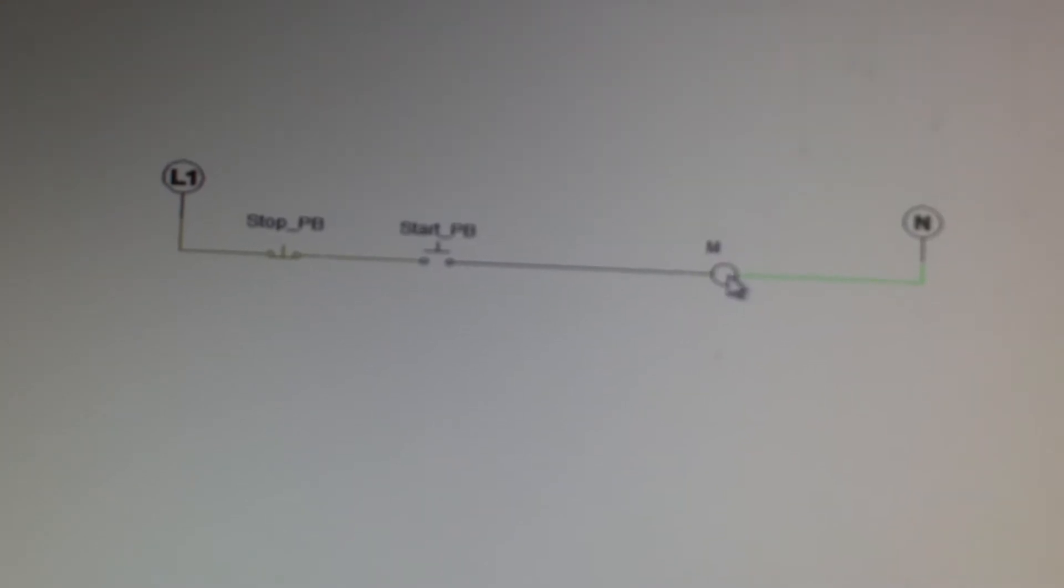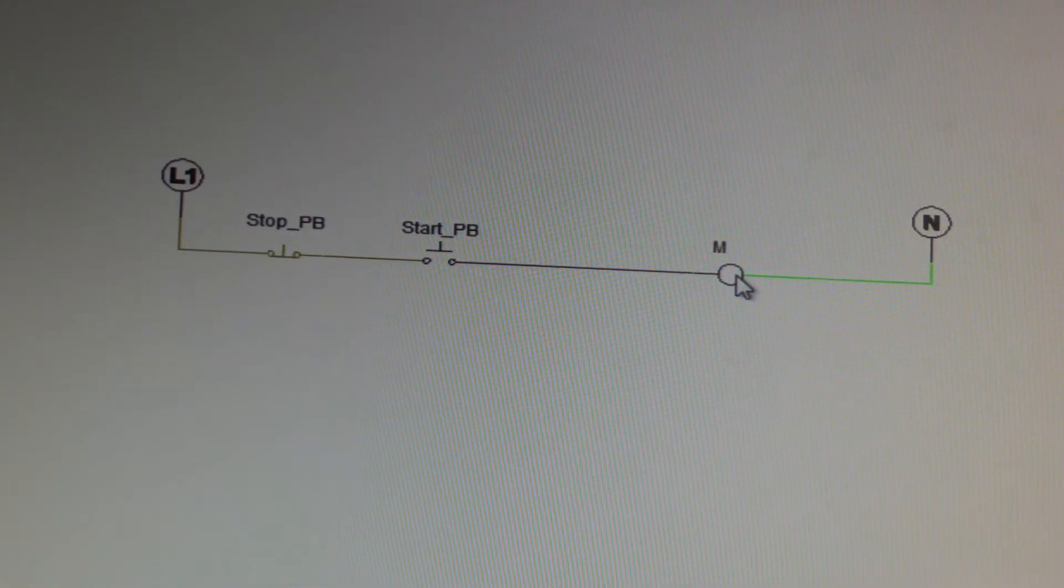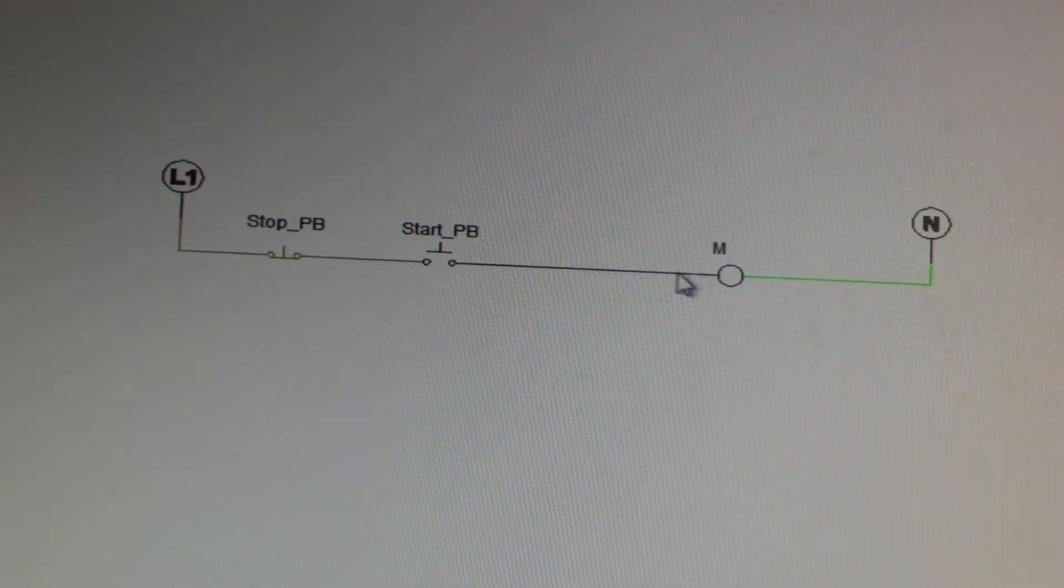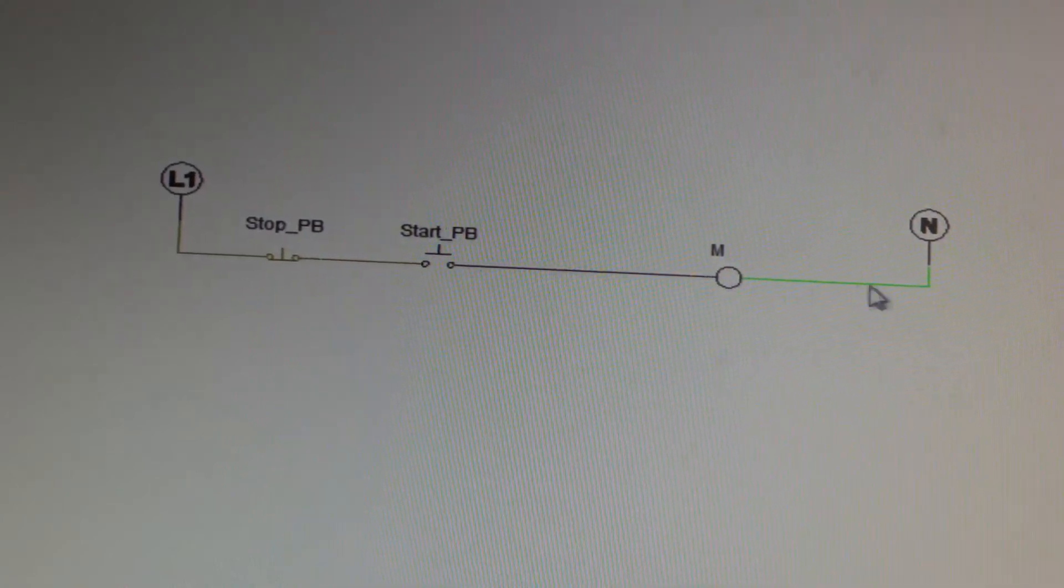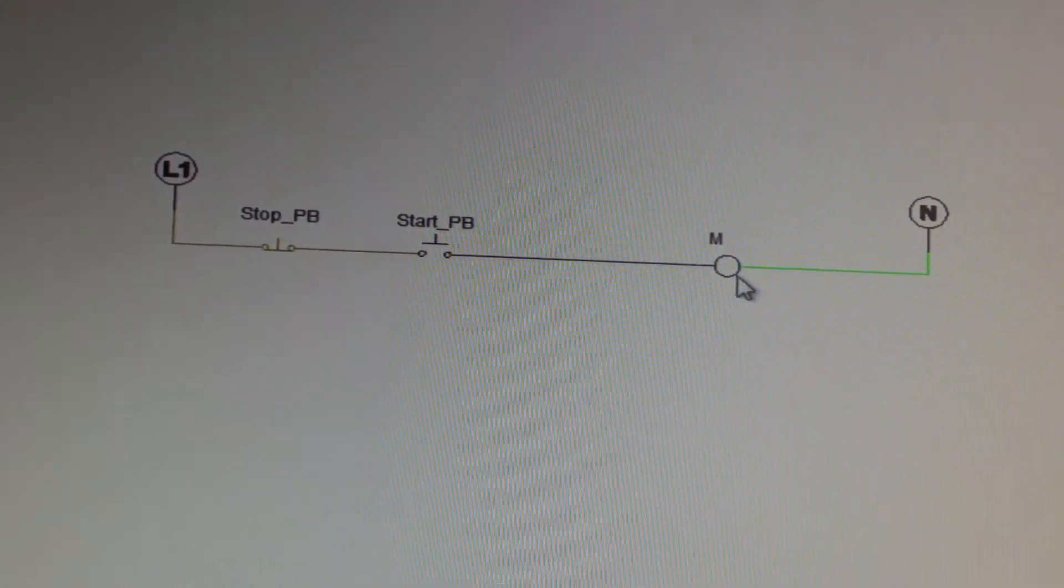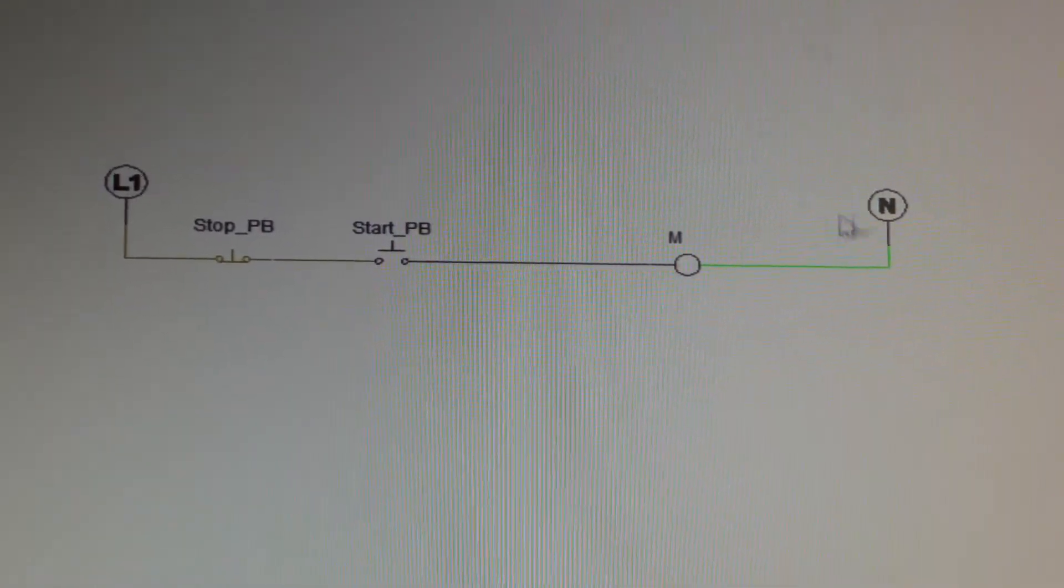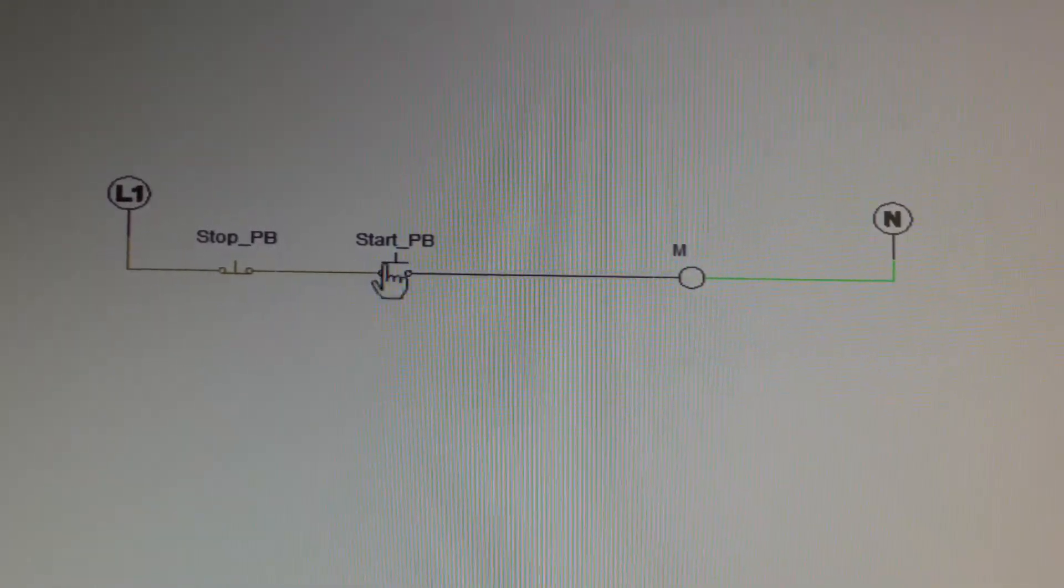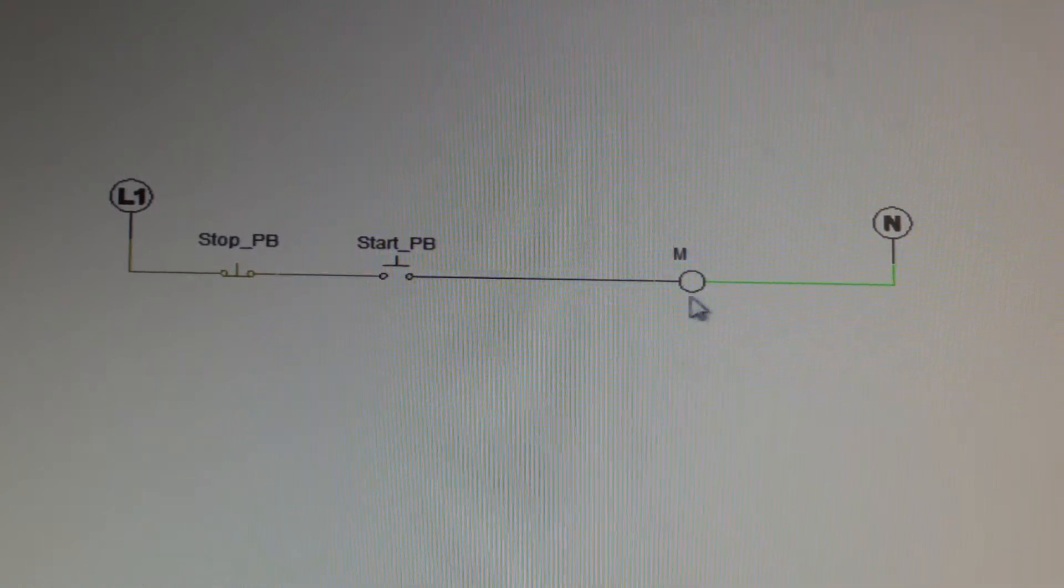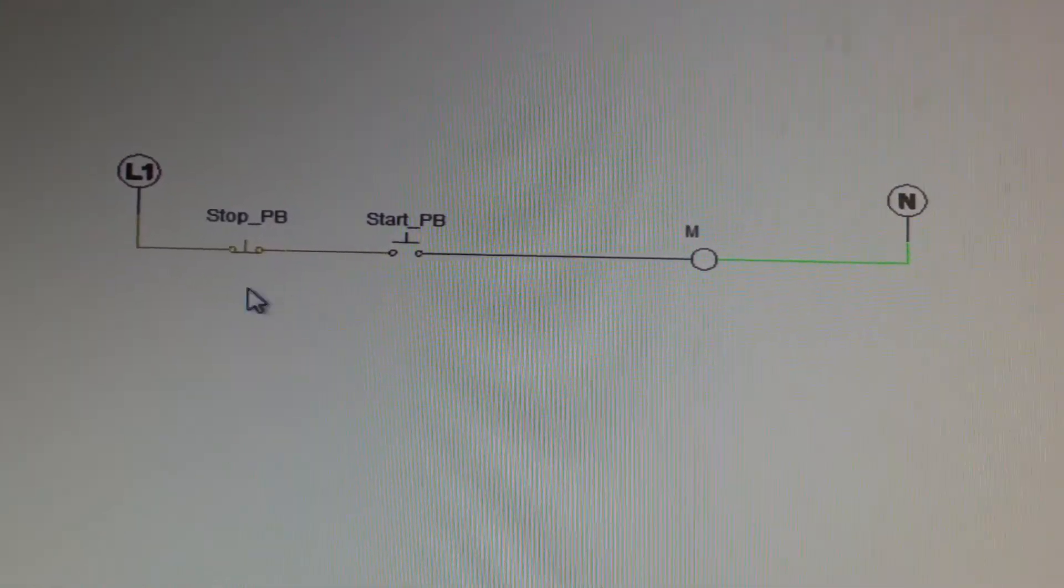Now over here is our coil. On our coils, typically you have an A1 and an A2, and when one side becomes energized and the other side is to our neutral, which is our potential difference from our 120, we actually have current flow all the way through. If we get through the stop button, start button, we will energize this coil here.